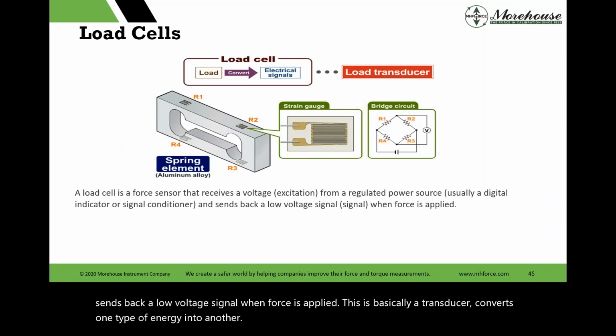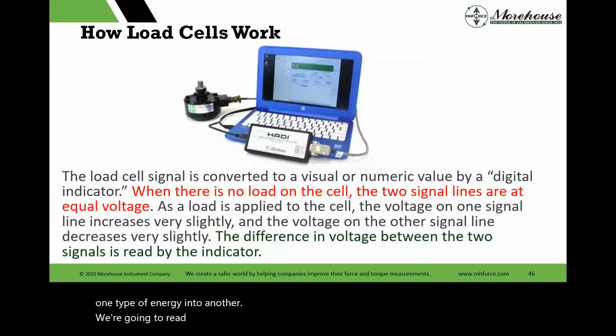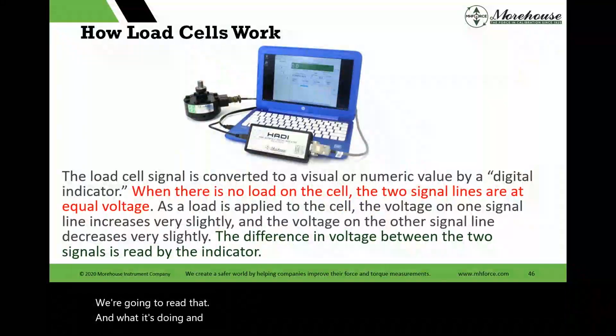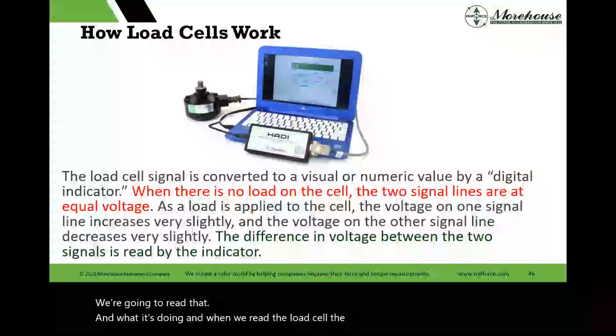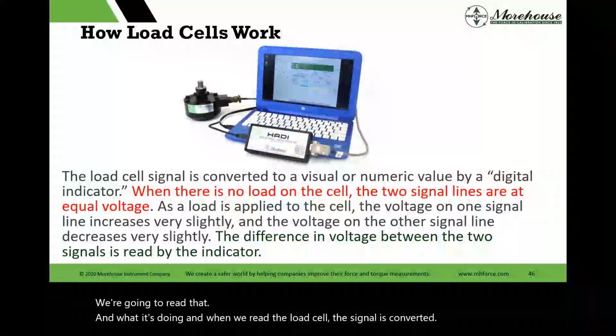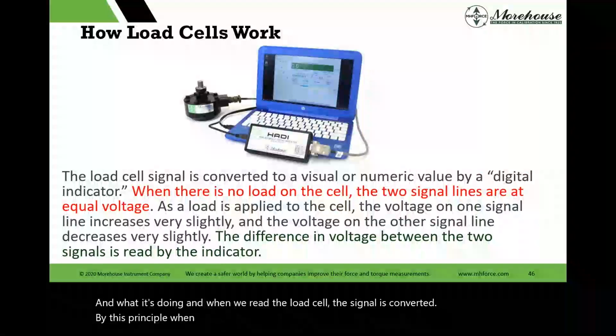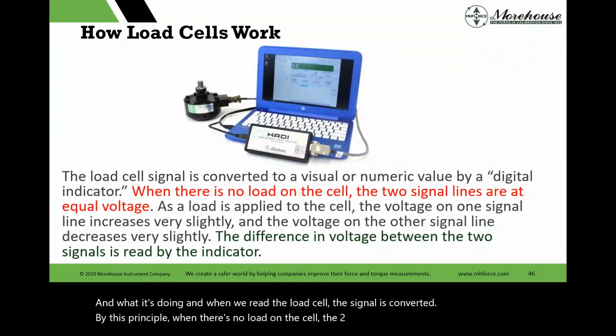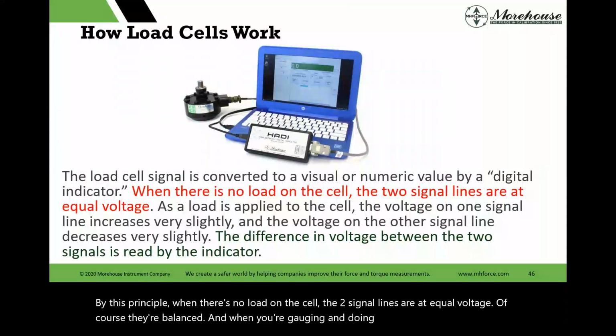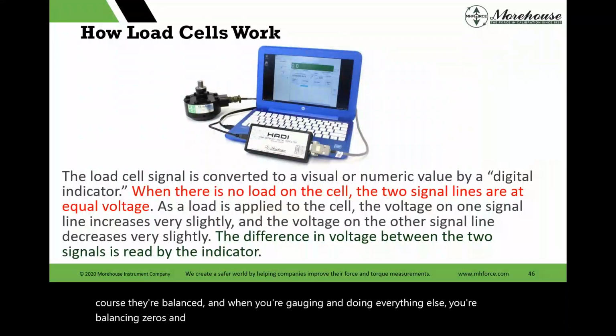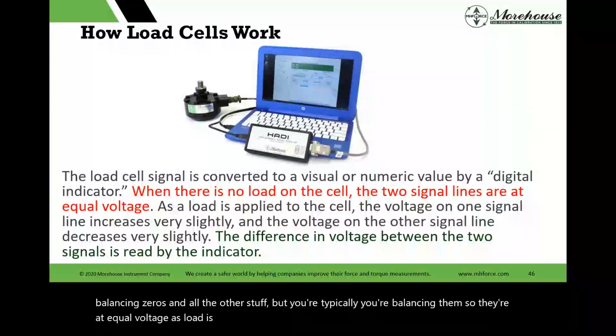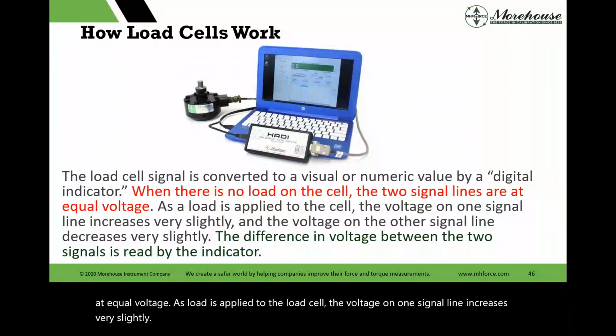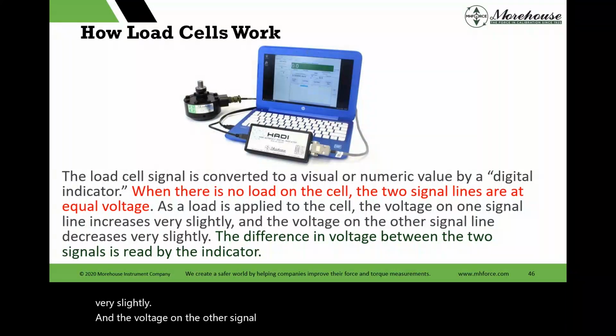We're going to read that and what it's doing. And when we read the load cell, the signal is converted by this principle. When there's no load on the cell, the two signal lines are at equal voltage. Of course, they're balanced, and when you're gauging and doing everything else, you're balancing zeros and all the other stuff. But you're balancing them so they're at equal voltage. As load is applied to the load cell, the voltage on one signal line increases very slightly, and the voltage on the other signal line decreases very slightly.